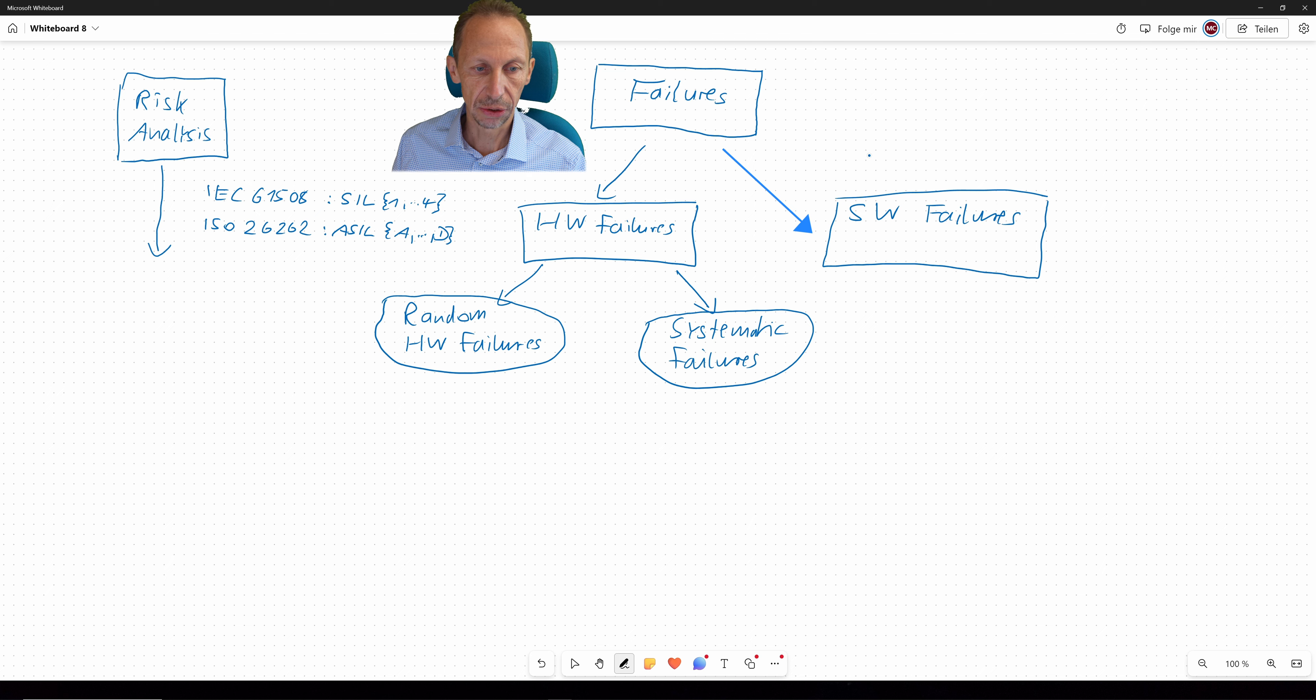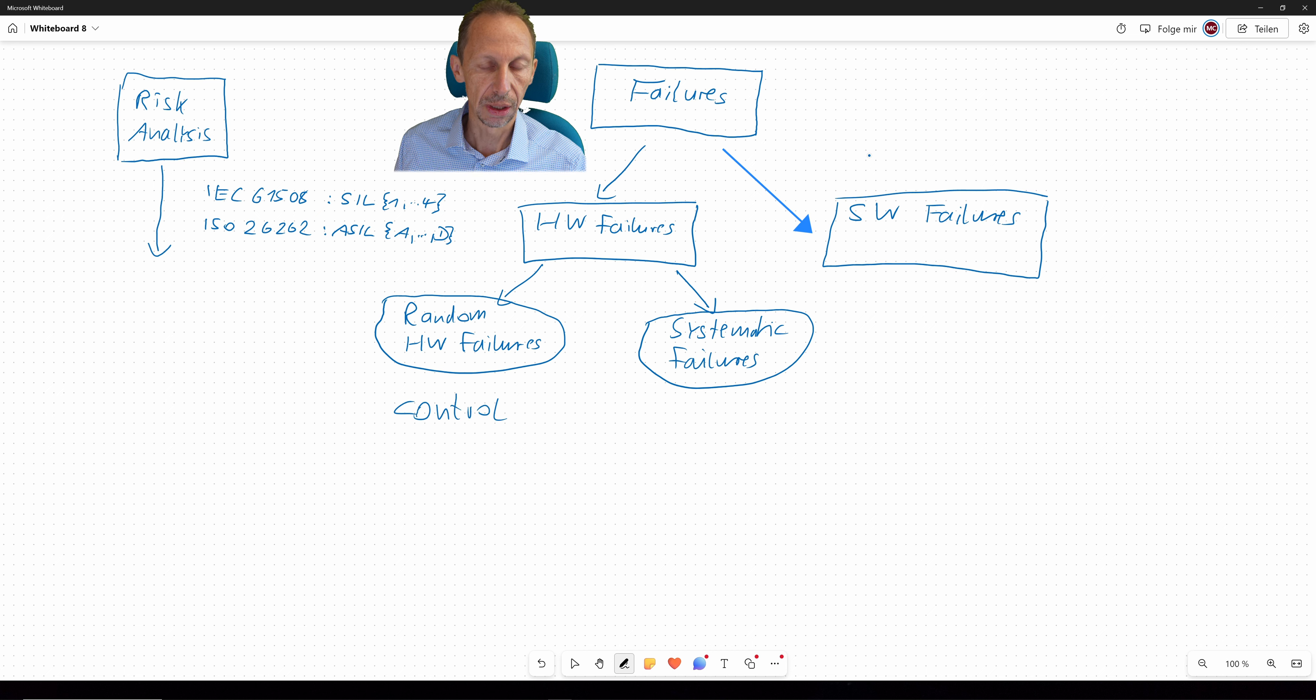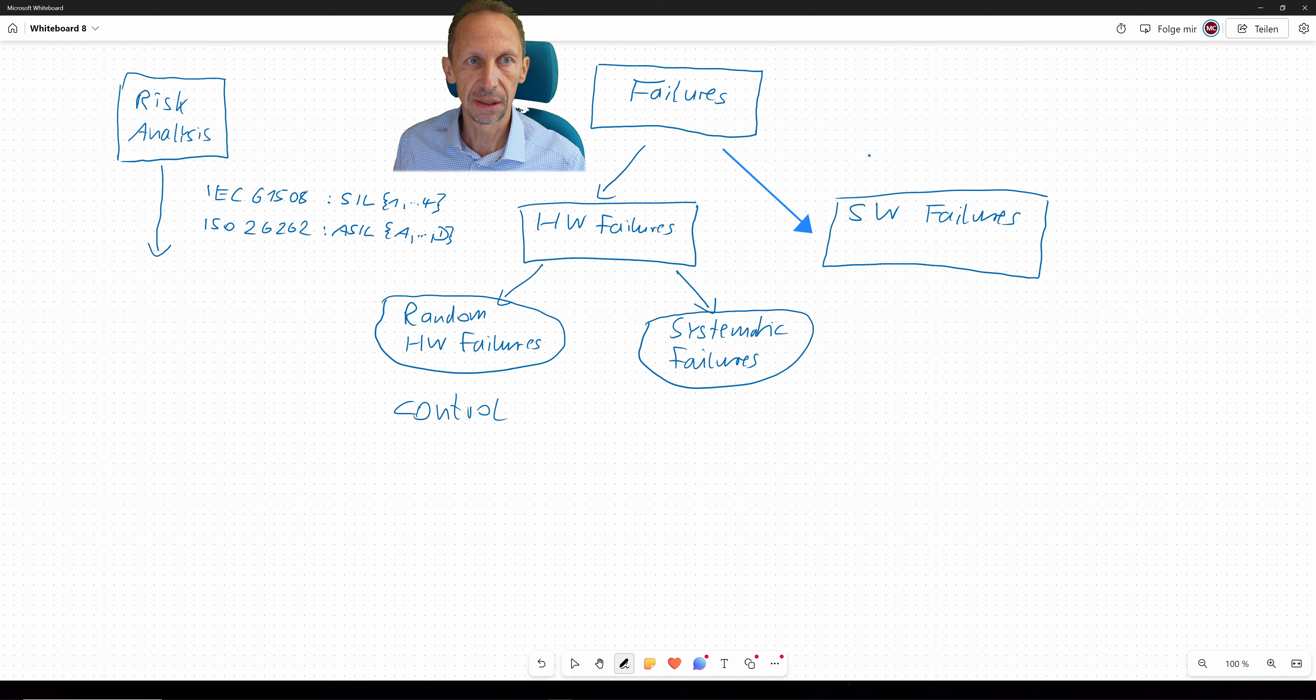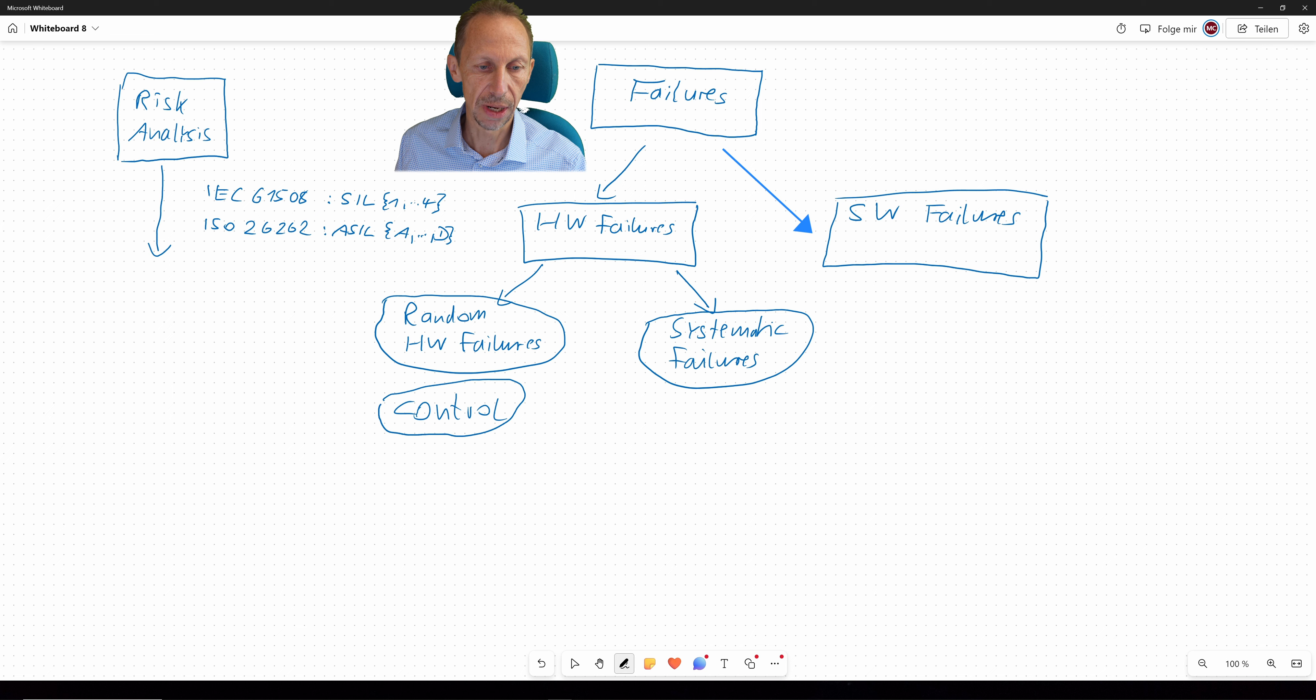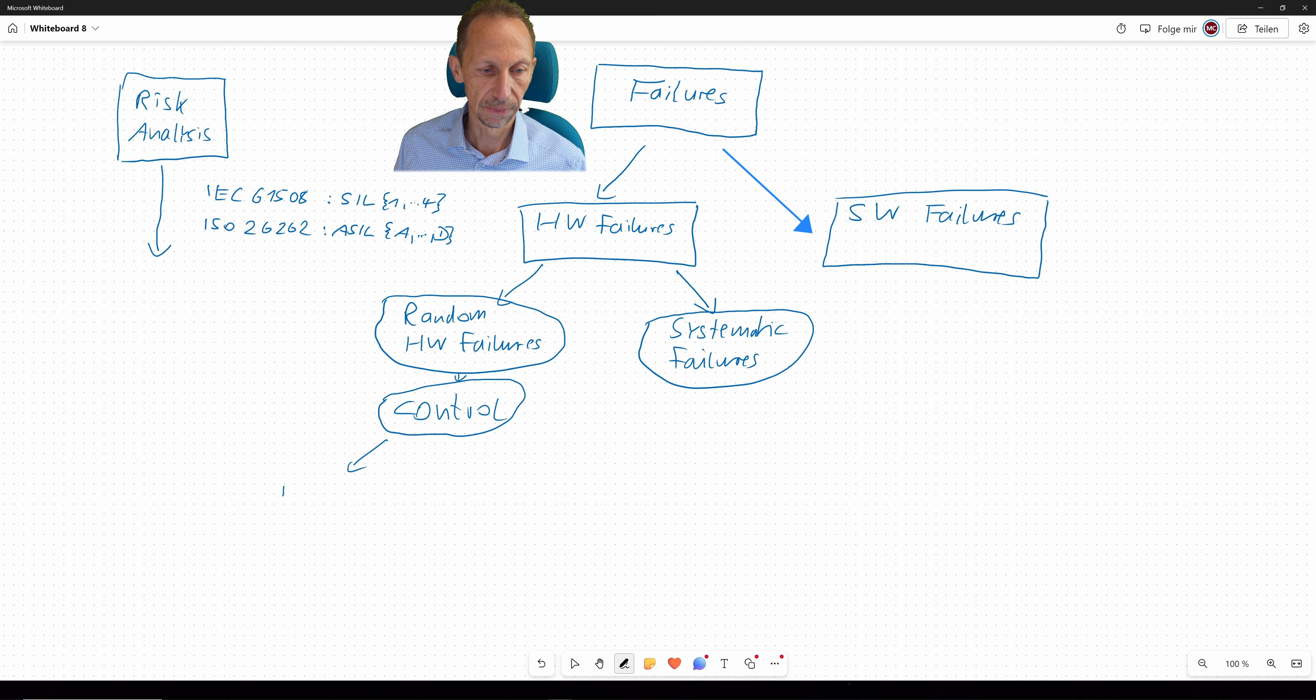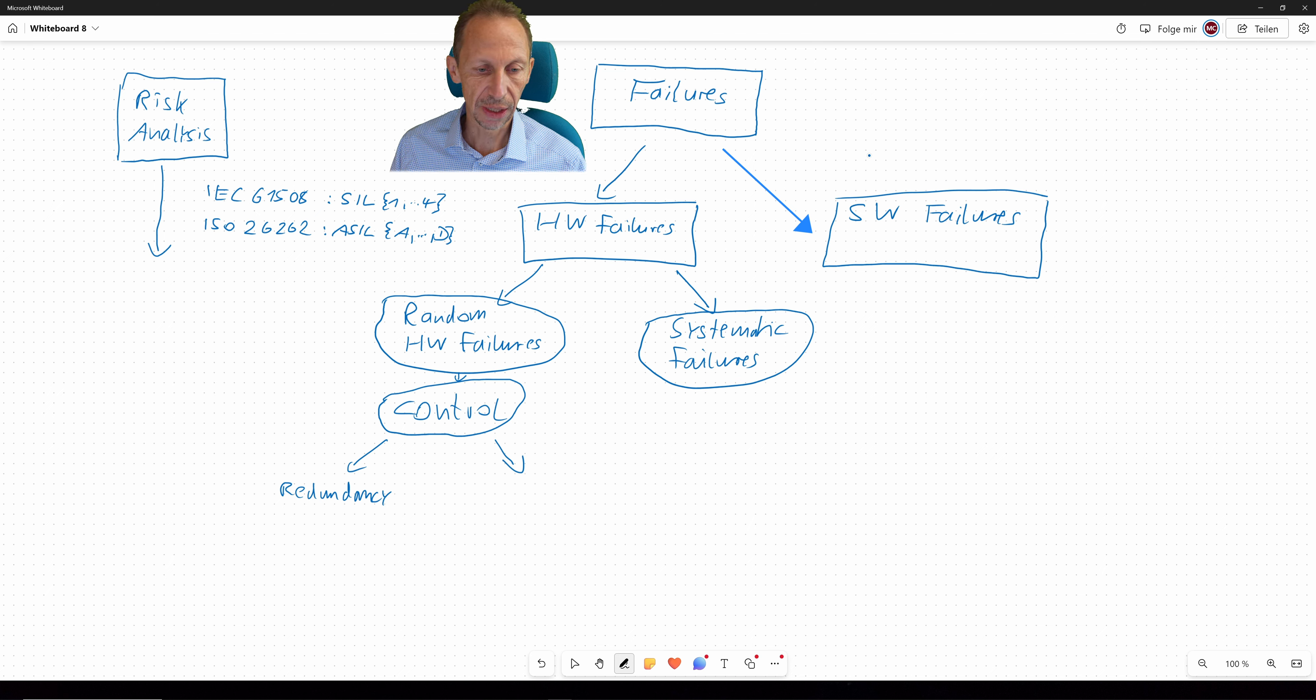And what about random hardware failures? What do we have to do here? We have to get them under control. So if a transistor burns, let's say being part of a driver stage driving a relay, then one measure in order to get this failure under control may be to have another channel. So another driving stage. So the main measures in order to get random hardware failures under control are redundancy and diagnostic functions.